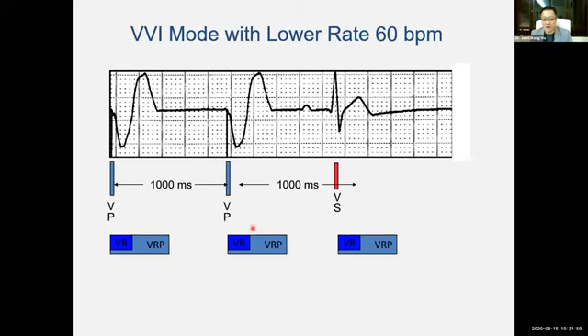So the pacemaker will tick for 1,000 milliseconds, 1,000 times, tick, tick, tick, tick, until 1,000 milliseconds, not sensing anything, you deliver another pacing spike and initiate another ventricular blanking period here. And the cycle continues. Now, it takes 1,000 milliseconds. Before the end of 1,000 milliseconds, something happened. The pacemaker picked up an intrinsic cardiac electrical activity from the ventricle. So ventricular sense. The same ventricular sense initiates another ventricular blanking period and ventricular refractory period here.